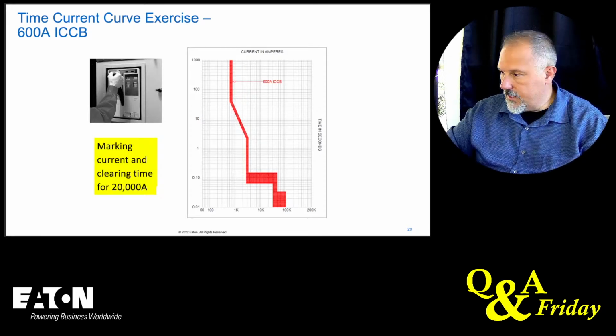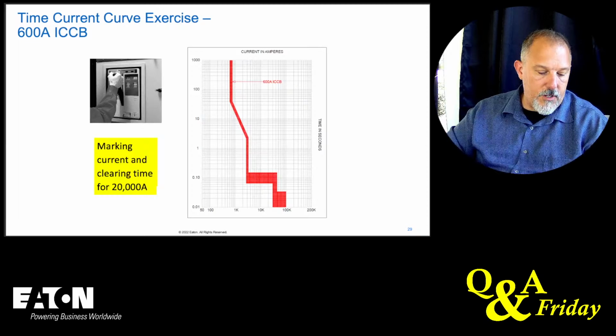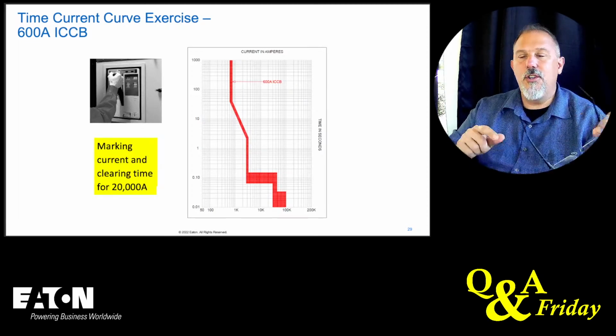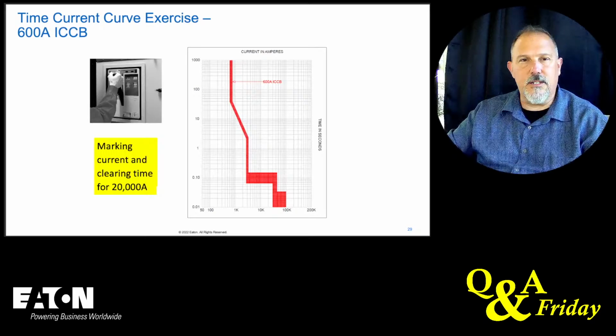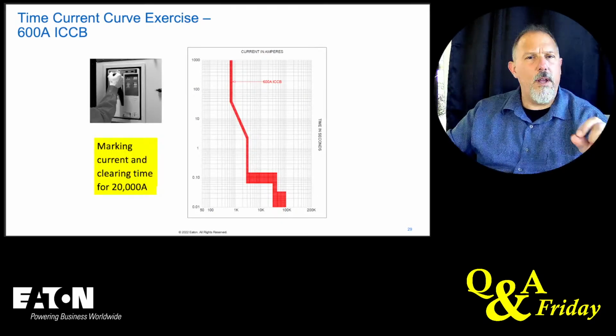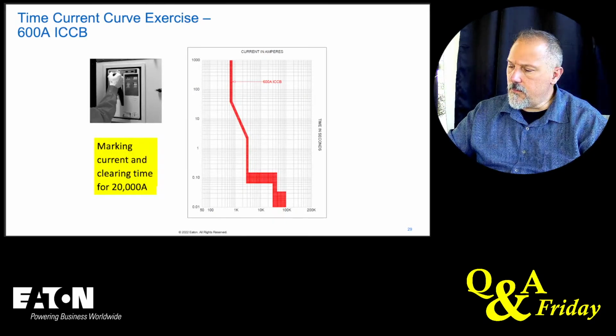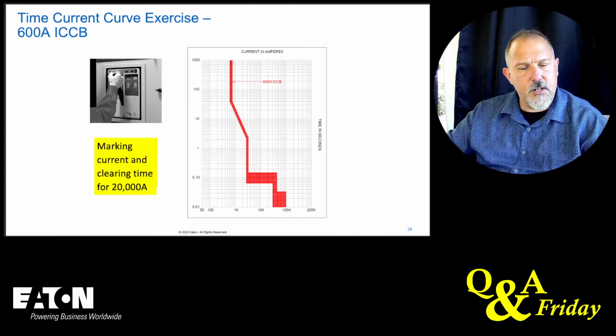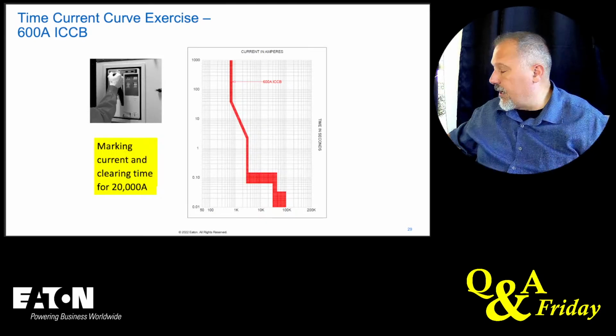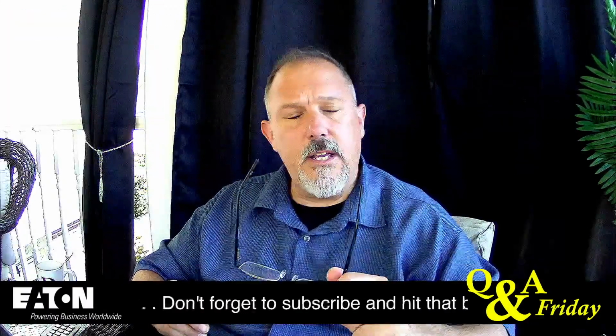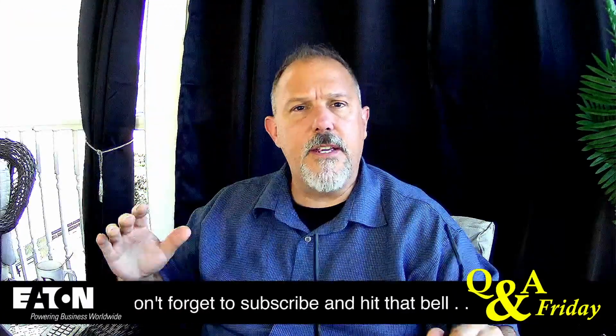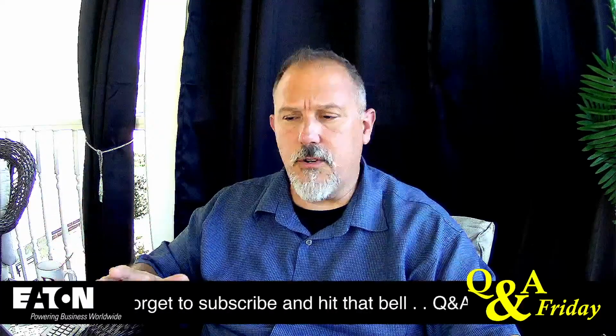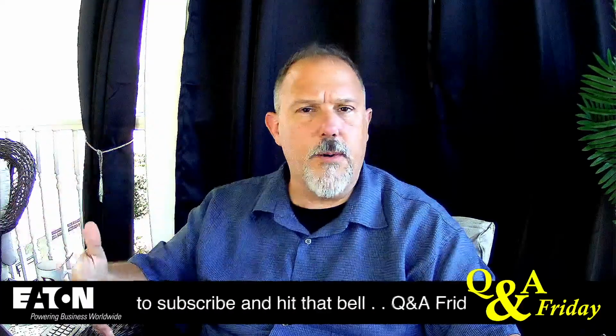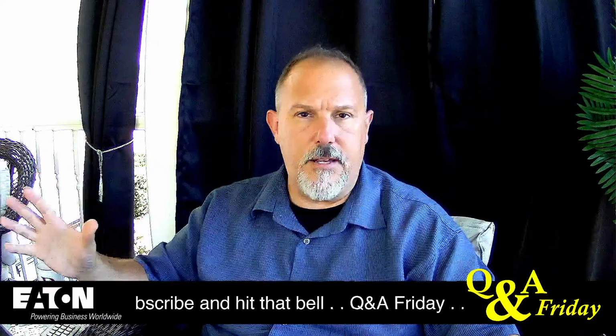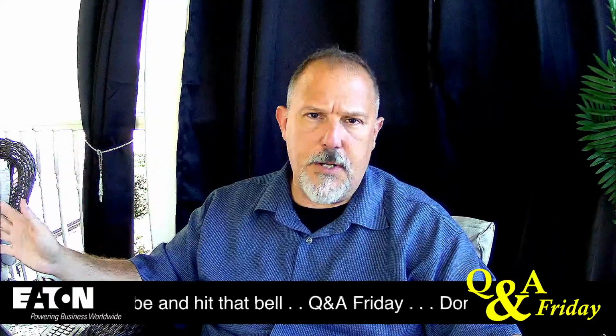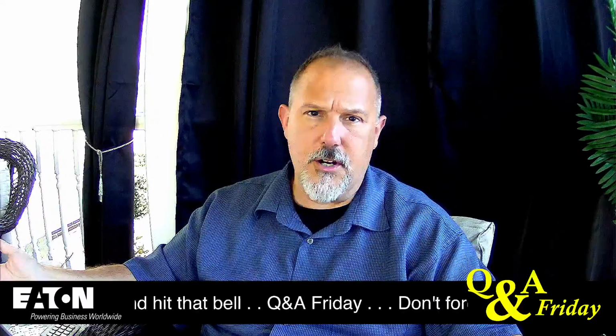So, what time is it? 1:47. So to answer this question, do we leverage the magnetic fields in any of these circuit breakers? We sure do. We have to always consider those magnetic fields. But an insulated case or a power circuit breaker is not current limiting in this instantaneous region, because of the time current characteristic, and power circuit breakers just get worse. So I'm not going to get over to the power circuit breaker aspect either. But if an insulated case circuit breaker is not going to be current limiting, a power circuit breaker is not going to be current limiting either, right?